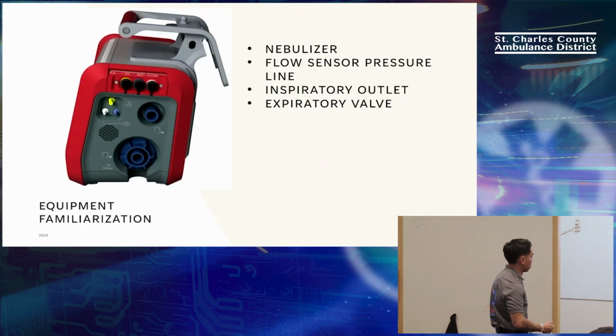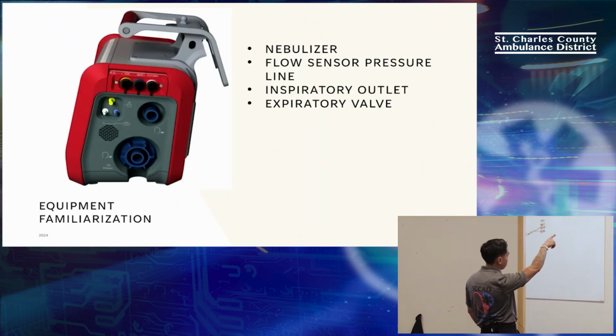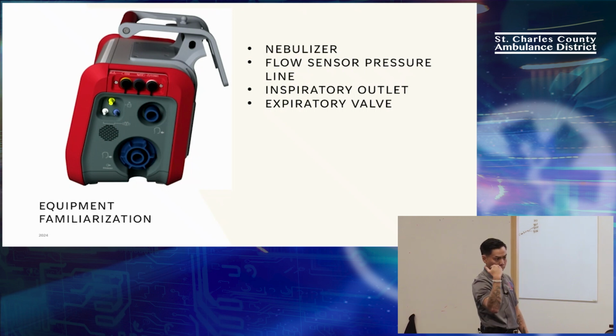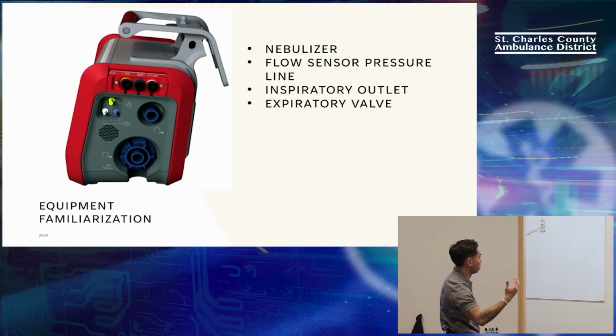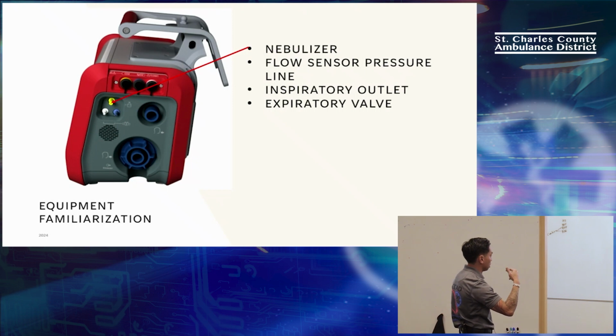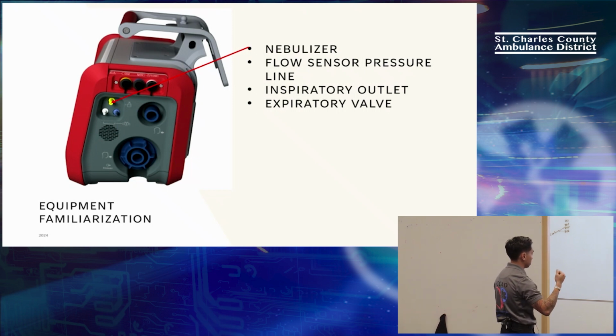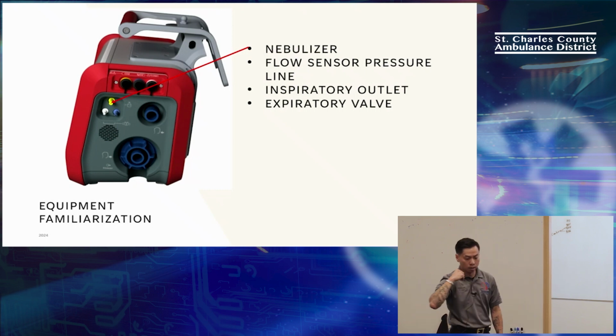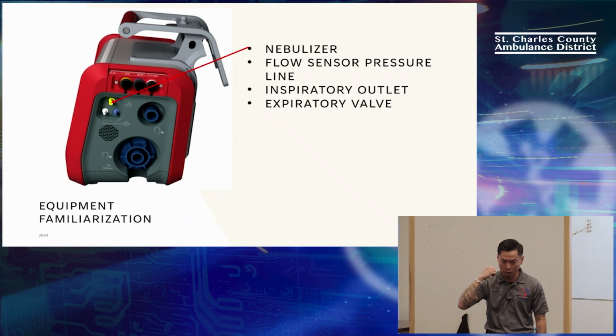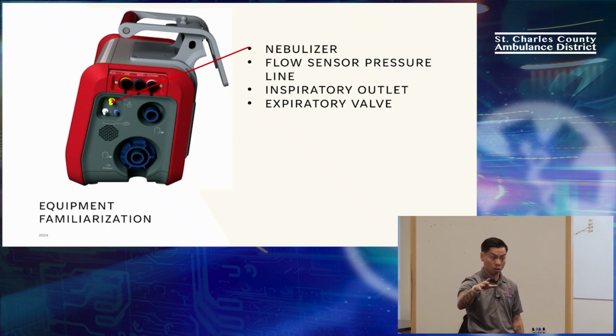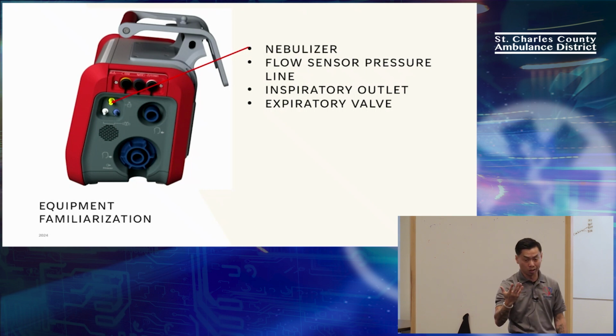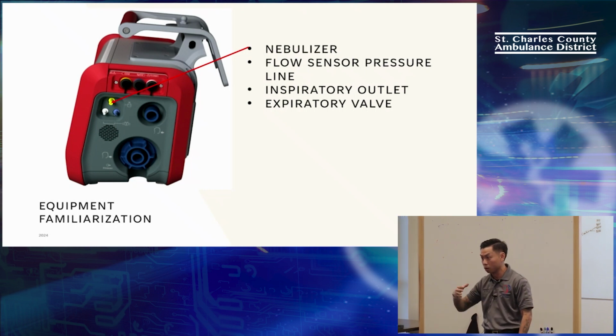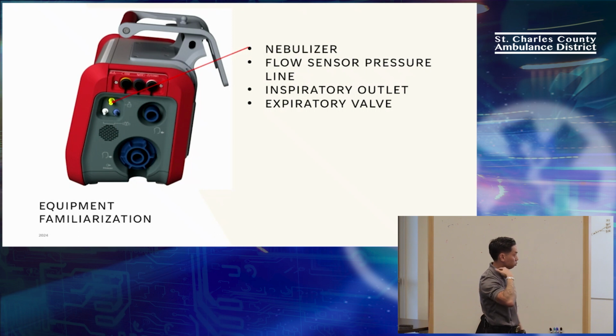All right, so this side of the ventilator. I know you see those 3 ports up there, and on ours, there's just a board over it because we don't have that module. But your neb treatment is going to plug into that yellow port. As opposed to plugging it into the wall, you'll plug the tubing into that yellow port, and it'll neb on inhalation. So every time the patient takes a breath, it sends the neb treatment. On exhalation, it just shuts off. So your neb treatments essentially last twice as long because you're not wasting nebs during the exhalation phase.